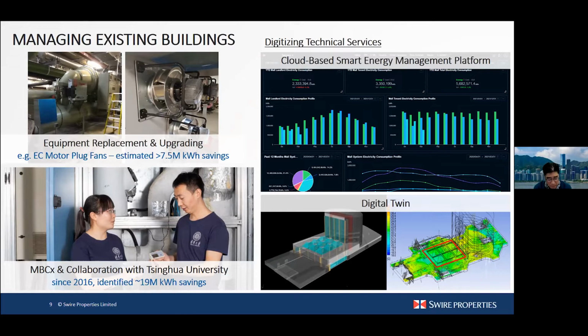We've also used a new technology called EC motor plug fans to replace centrifugal fans in most of our air handling units. This immediately saves at least about 30% of the fan energy in each unit. If the AHU or building system has a less efficient fan operation, you can easily achieve over 40% saving simply by replacing the fan. These are all measures from our experience in the past 2 or 3 years.